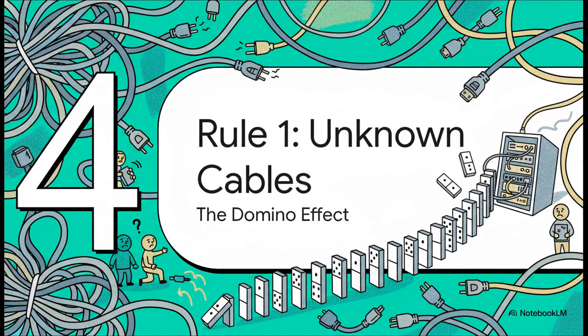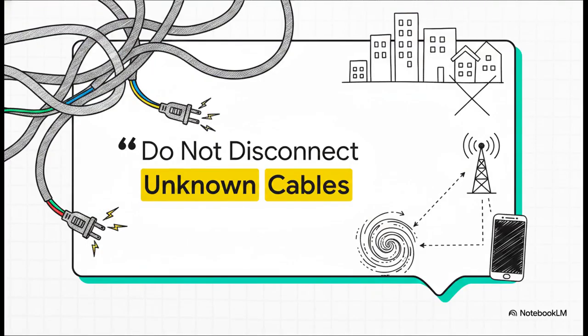Moving on to Section 4, Rule 1, Unknown Cables and the Domino Effect. Now that we know the hardware, let's step into the human element and the absolute non-negotiable operational boundaries, starting with cables. You can have the best generators and cooling systems in the world, but human error can bring it all crashing down in seconds. This rule is absolutely ironclad. Do not disconnect unknown cables.